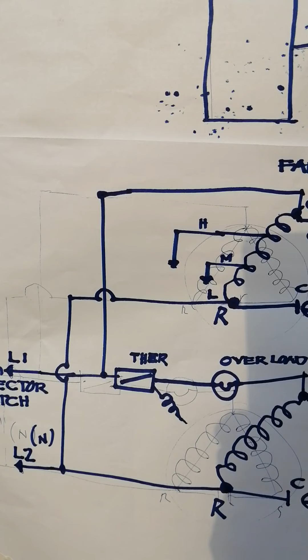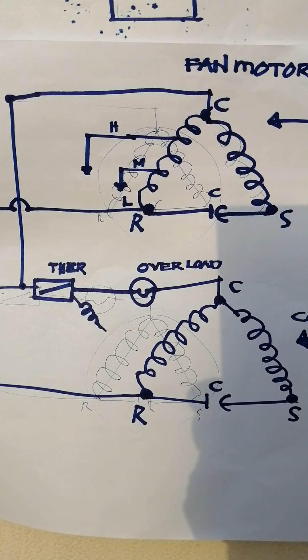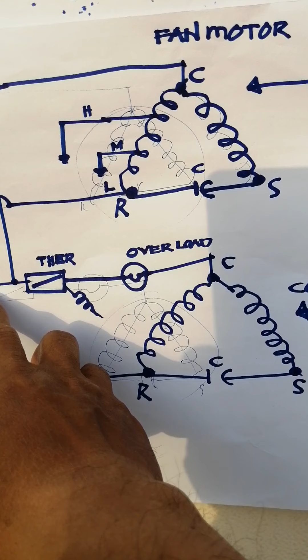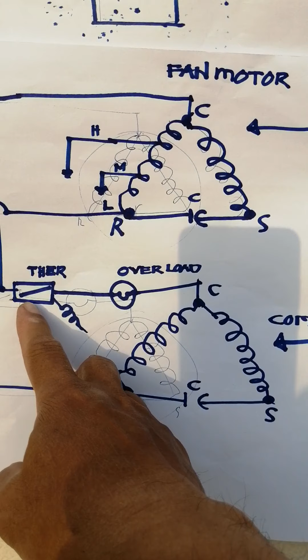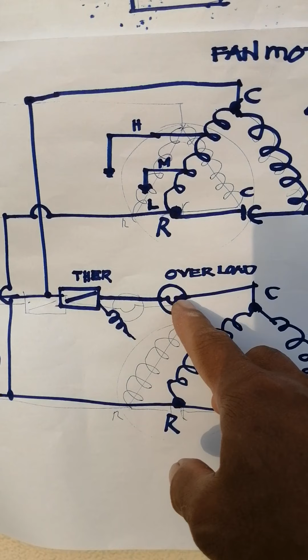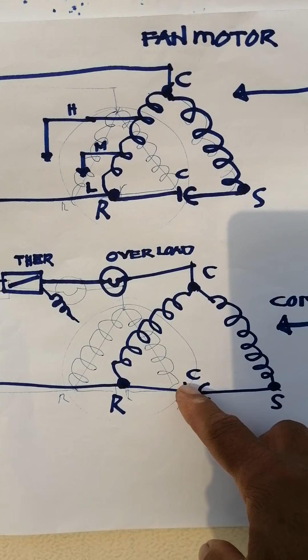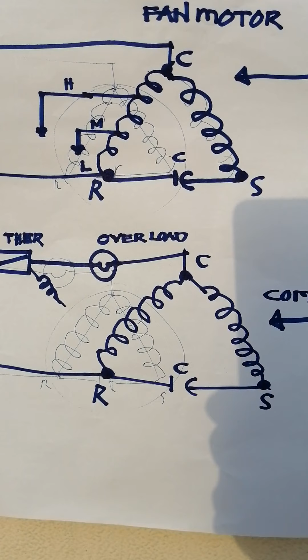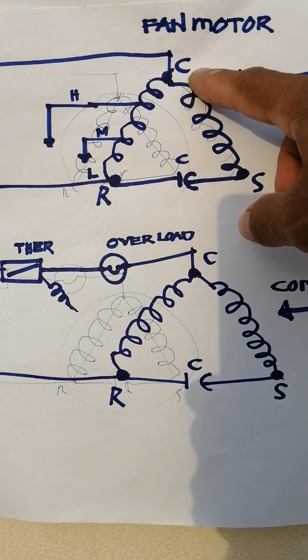Now we will see if our fan motor is running, but our compressor is not running. What is the possible cause? So we will not check the voltage because the motor is already running normally, so we focus on the compressor. As you can see here, the line of the compressor goes to the thermostat, then after the overload, maybe some of this one is open. That's why the compressor will not run. Otherwise, the capacitor is also defective.